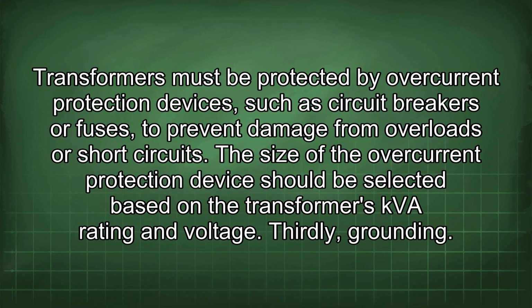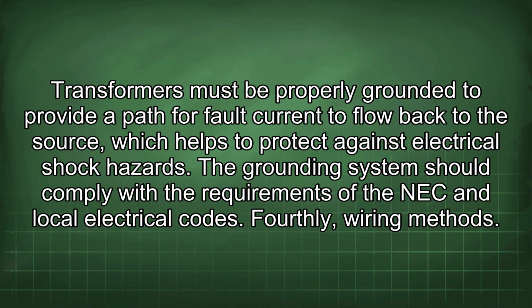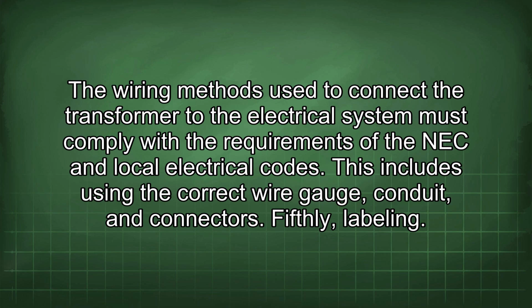Thirdly, grounding. Transformers must be properly grounded to provide a path for fault current to flow back to the source, which helps to protect against electrical shock hazards. The grounding system should comply with the requirements of the NEC and local electrical codes. Fourthly, wiring methods. The wiring methods used to connect the transformer to the electrical system must comply with the requirements of the NEC and local electrical codes. This includes using the correct wire gauge, conduit, and connectors.